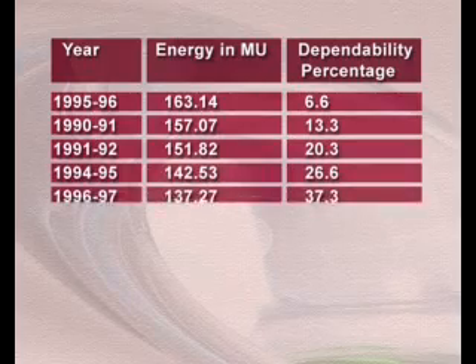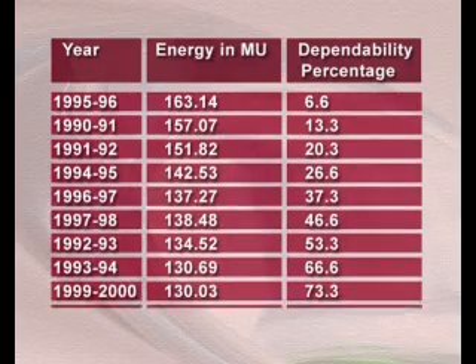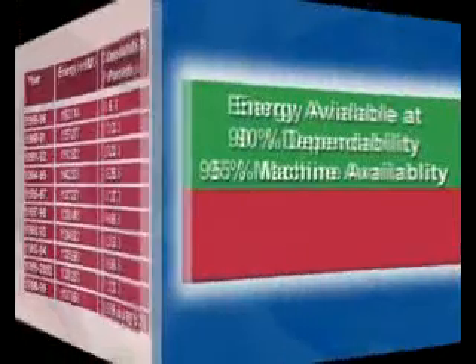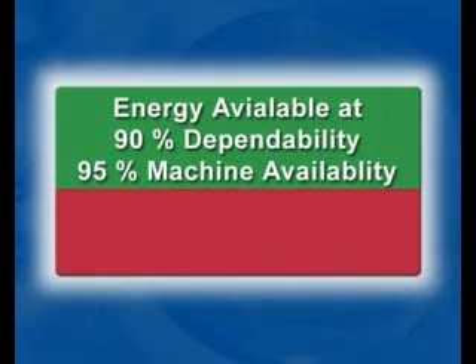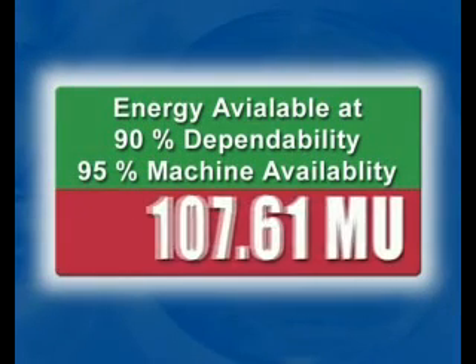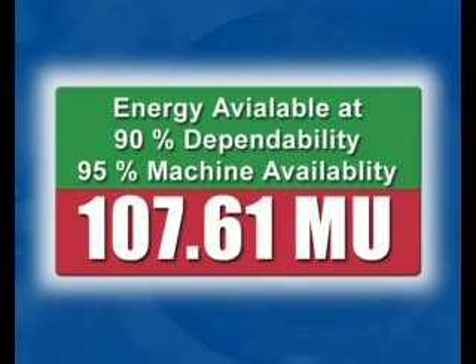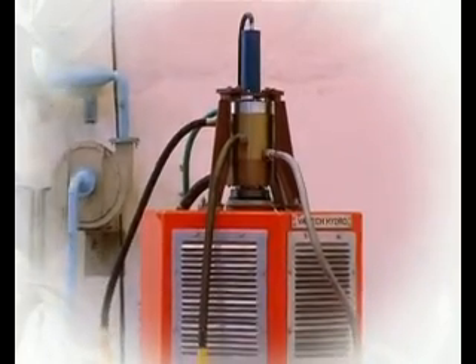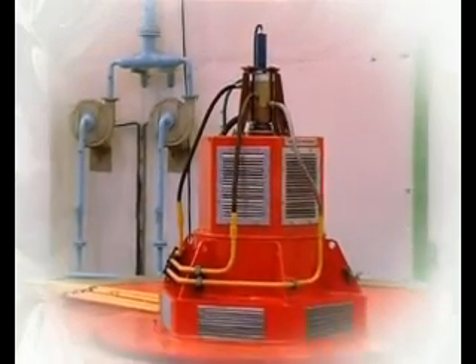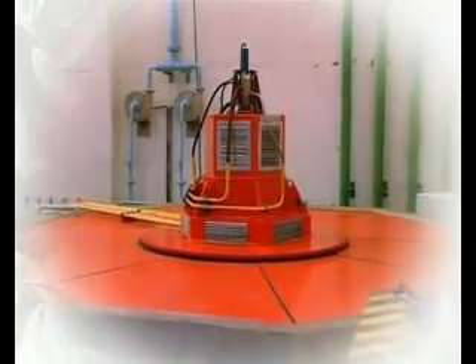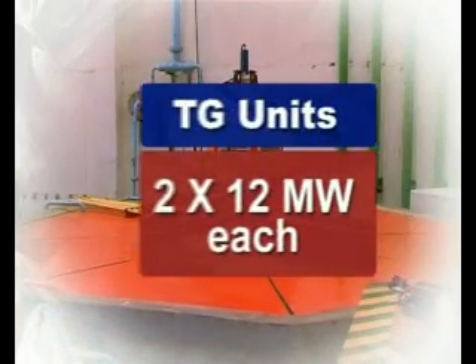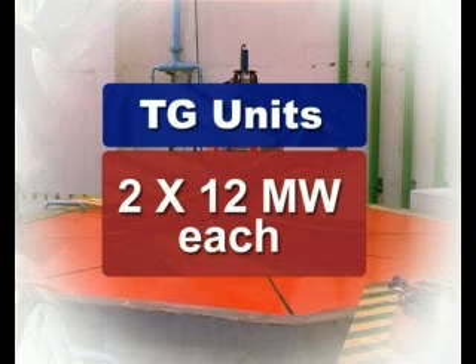Energy dependability studies are carried out for the project and the annual energy during 15 years period is tabulated. Energy available at about 90% dependability with 95% machine availability is 107.61 million units and the same is adopted in financials of the project. Various combinations were worked out to decide on number of units required for 24 megawatts of generation. On techno-economic considerations, two units of 12 megawatts each are found to be suitable as they can fully exploit the maximum power potential available in this scheme.